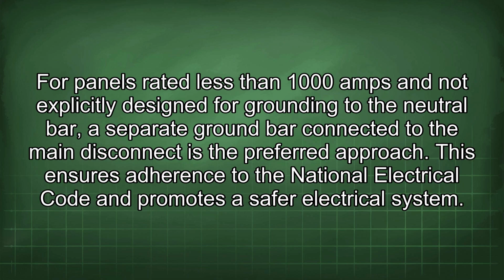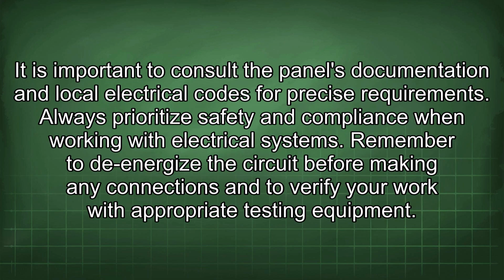For panels rated less than 1000 amps and not explicitly designed for grounding to the neutral bar, a separate ground bar connected to the main disconnect is the preferred approach. This ensures adherence to the National Electrical Code and promotes a safer electrical system. It is important to consult the panel's documentation and local electrical codes for precise requirements. Always prioritize safety and compliance when working with electrical systems. Remember to de-energize the circuit before making any connections and to verify your work with appropriate testing equipment.